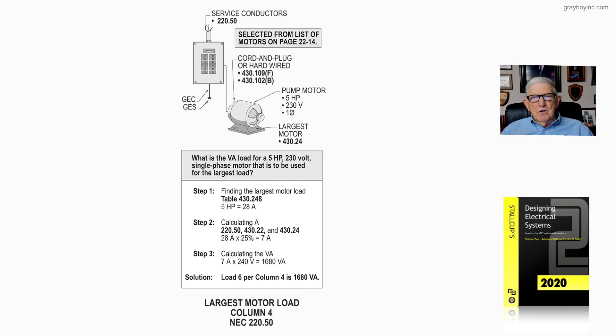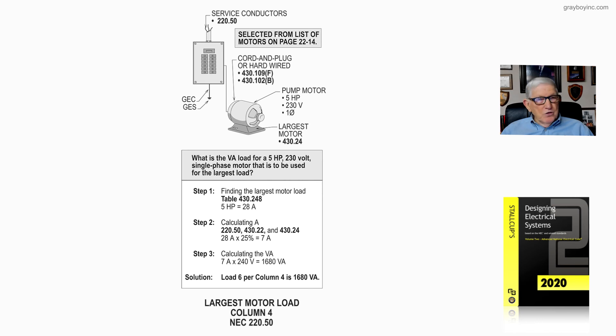To convert that to VA, we take 240 volts — single phase motor — times 7 amps, and we come up with 1,680 VA. So basically, load 6 in column 4 is 1,680 VA.